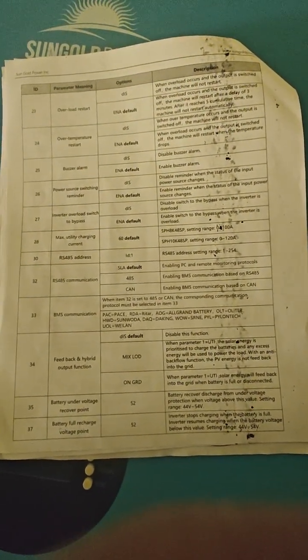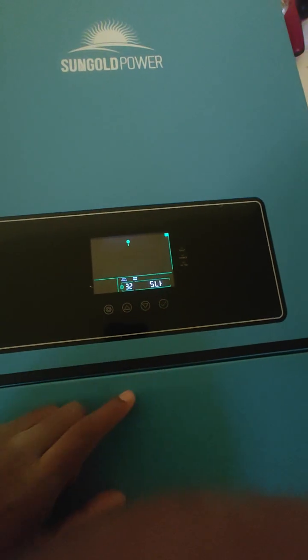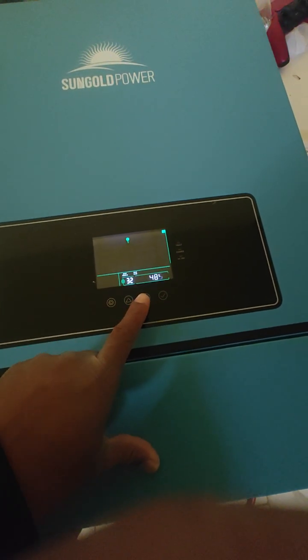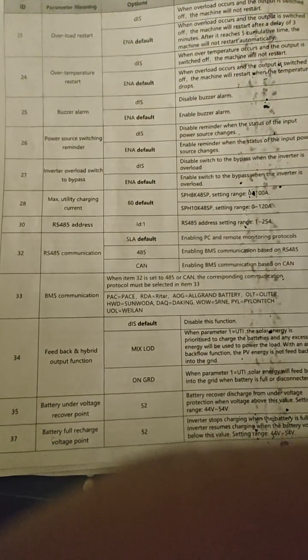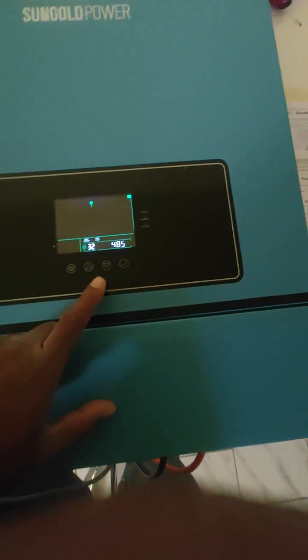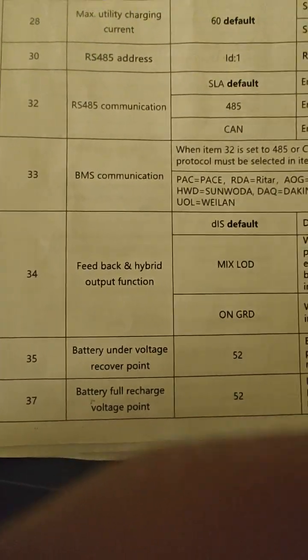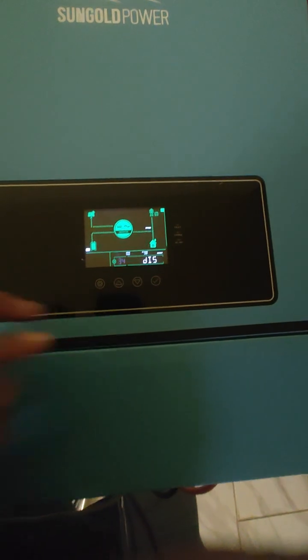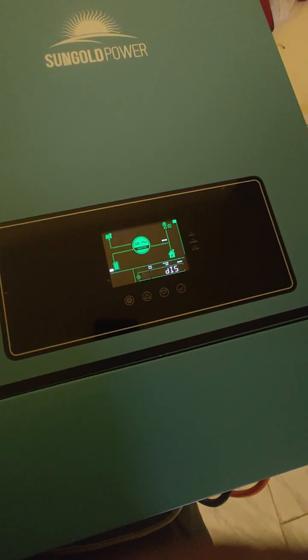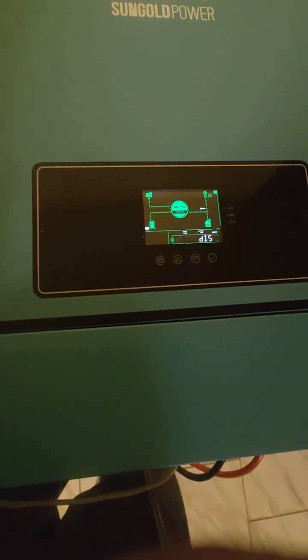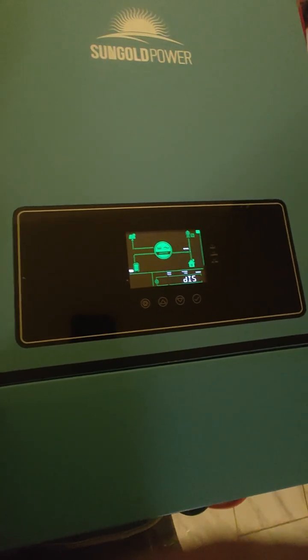32. RS485 communication. SLA is the default, but we are going to be using 485. 33. BMS communication. These batteries use Pylon Tech, PYL, so that's what we're going to set. And looks like that's already done. 34. Feedback and hybrid output function. That is disabled, so we don't want any feedback to the grid. As this is Africa, I have no idea how that would work there, but let's just keep it disabled before we blow something up.